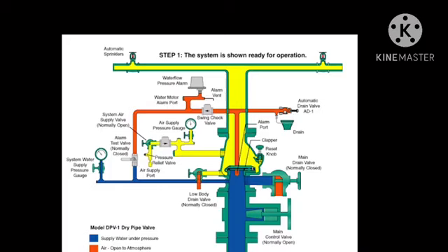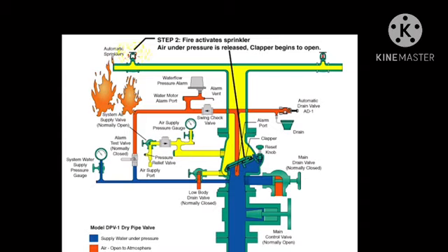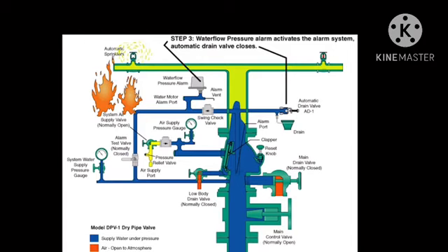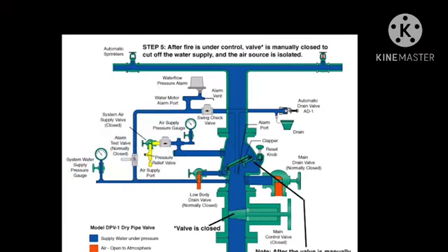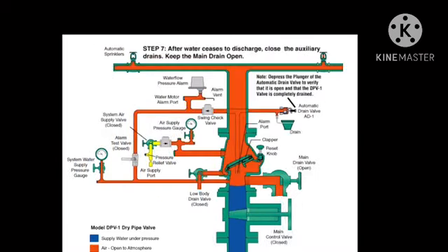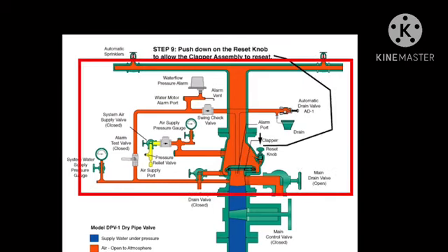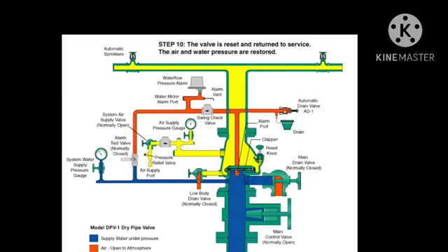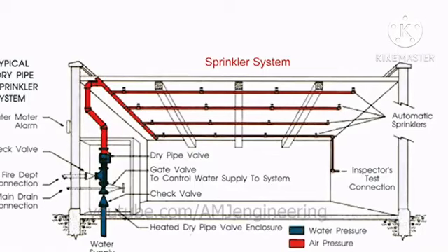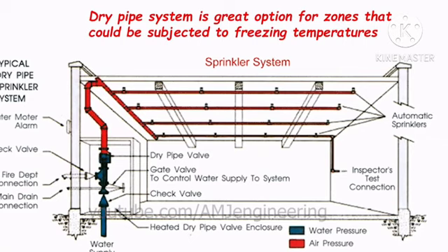Like a wet pipe system, when the temperature at the ceiling becomes hot enough, the glass bulb or fusible link of the sprinkler breaks. However, in this case, water isn't immediately available because the pipe is not water-filled. Instead, air is released from the now open sprinkler head. This creates a drop in pressure, causing the dry pipe valve to open and water to fill the system. Water will then flow from the open sprinkler head. Since there is a delay between sprinkler operation and water flow, the size of dry pipe systems is limited. The size limitation is intended to minimize the amount of time water delivery is delayed. A dry pipe system is a great option for unconditioned spaces, or locations where the temperature of the space cannot be guaranteed to be high enough to prevent water in the system from freezing.